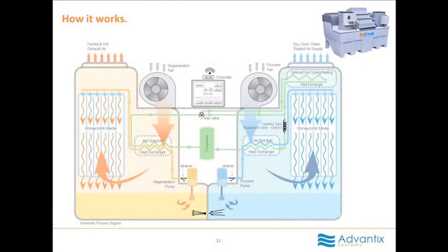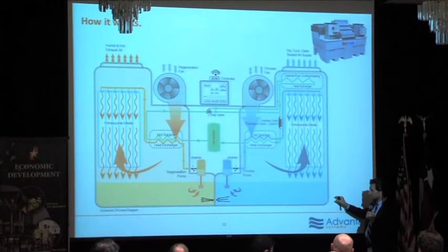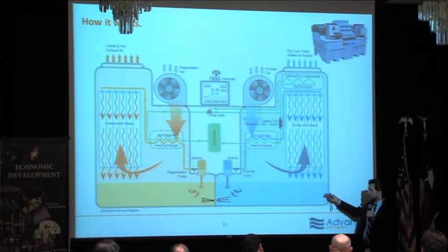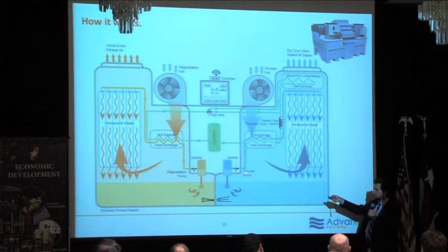So there's never an issue of maintenance in terms of the effects of sludge or anything happening at the bottom of this. If you are, people say, if I'm next to a gravel quarry, am I going to have extra maintenance? Yes, you definitely are. This sump is designed to accommodate where the solution will flow and come to rest before recirculating. That's designed to accommodate some sediment coming out of the air. You're going to pick up particulate, the heavier stuff settles to the bottom, the finer stuff goes into that strainer.